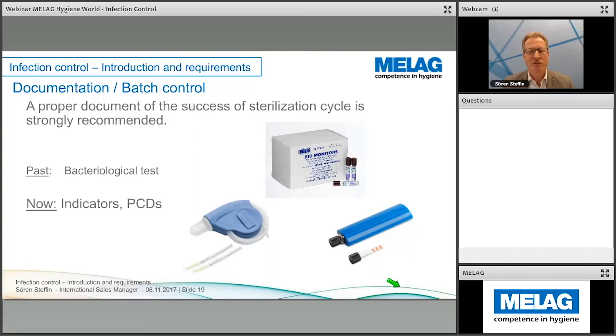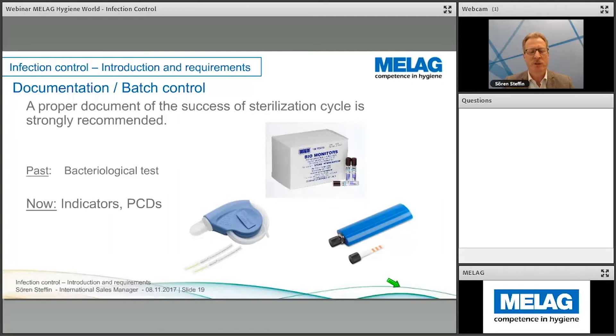Following the daily demands and the higher level of infection control systems, authorities demand a cycle check — for instance by chemical indicator systems or process challenging devices. We know the Melacontrol system, for instance the so-called helix systems. We know indicator strips to bring immediate evidence of a successful cycle. There is still a discussion about indicator systems for washer disinfectors, and it is not finished so we cannot make any recommendation there. But for sterilization, helix systems are well known and quite often used as an independent source for a safe sterilization result.